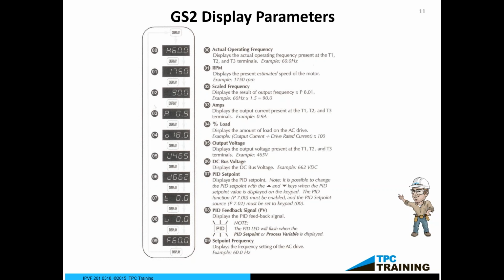So the actual operating frequency, the RPM, the scale frequency, that's just a multiplier. The different current levels, the percent of load. And you say percent, how does it do that? It calculates the percent of load. Output current, what the rated current is, then you can set these up. So if you put the rated current at 5 amps and it's running 2.5 amps, it's going to tell you the percent of load. Setting these little rascals up is very, very easy once you know the addresses in which you're supposed to set them up. Not difficult, it just takes a little bit of time to go through those unique addresses to program these.